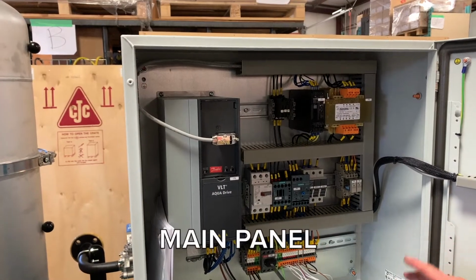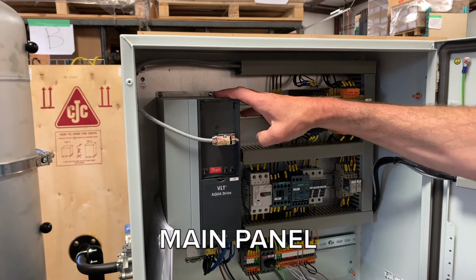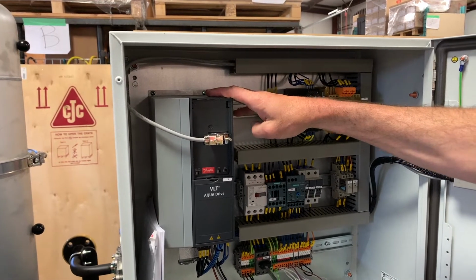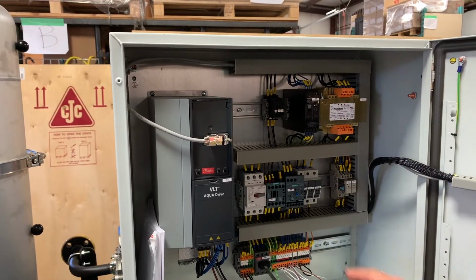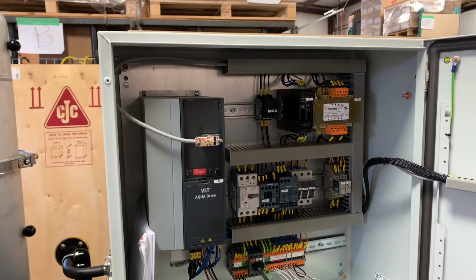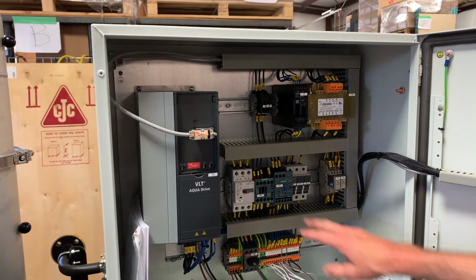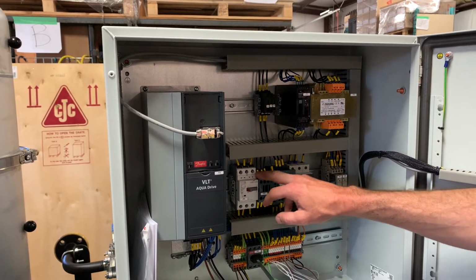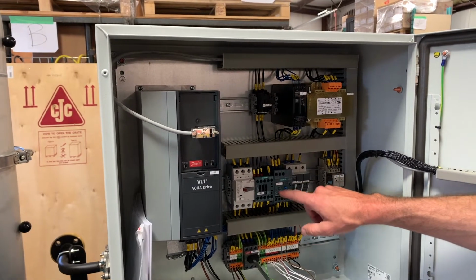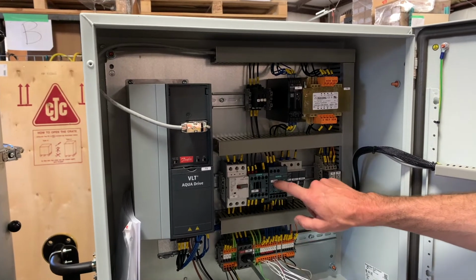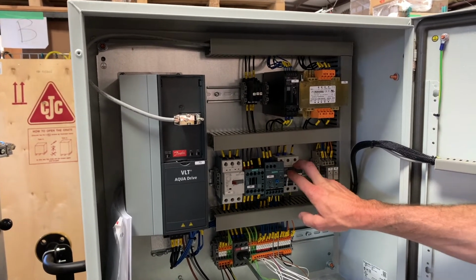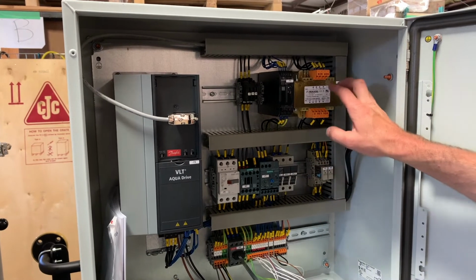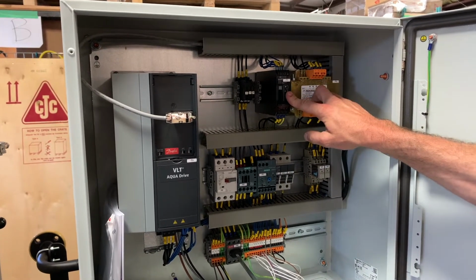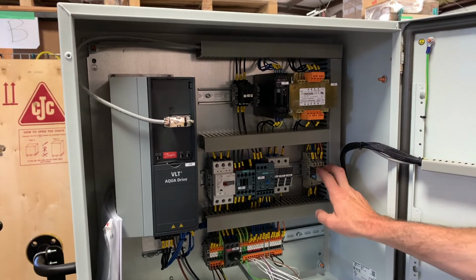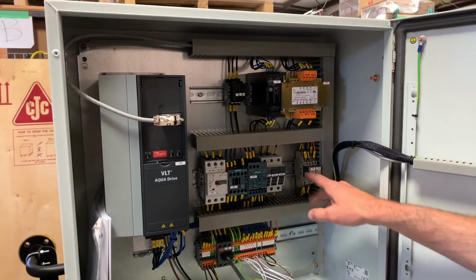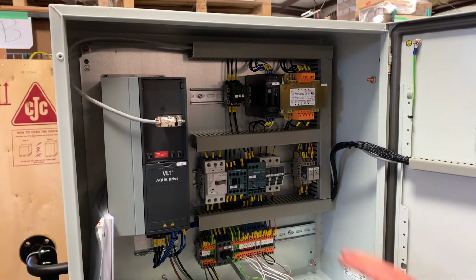Inside our panel, we have our main components. This is the variable frequency drive for the pump motor. This automatically adjusts based on the temperature of the oil, so to try and get our maximum cooling effect. We've got our circuit breaker feeding the frequency drive. We've got our fan contactor here with the overload and fusing for the fan motor. We've got a transformer and power supply for our control circuit, and just a couple of relays measuring the temperature incoming and for when to change the speeds on the pump.